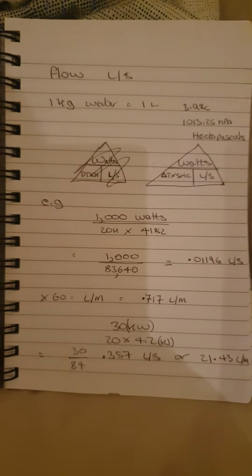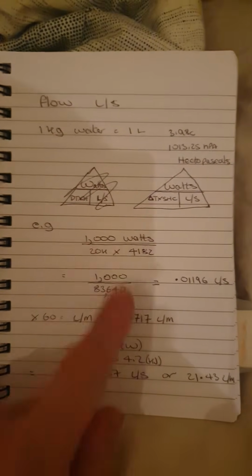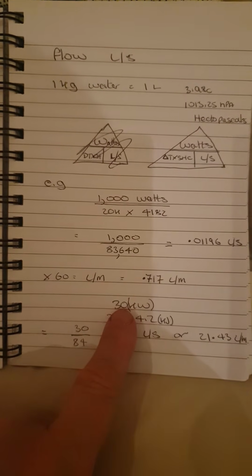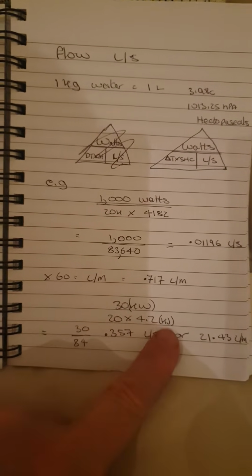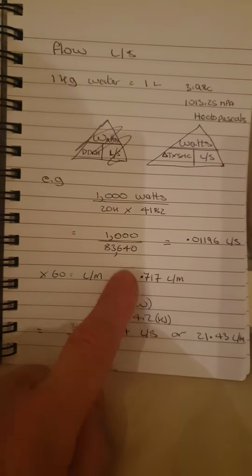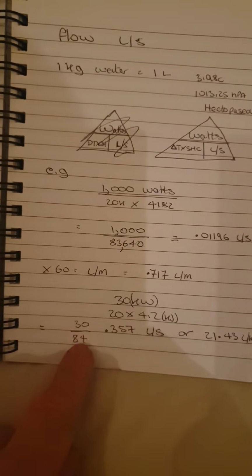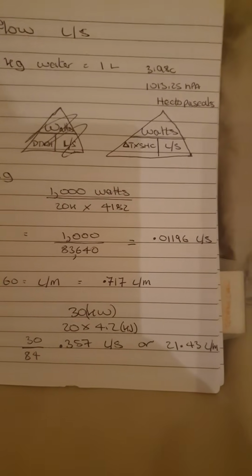Right, if you think in terms of a 30 kilowatt boiler then, rather than a 1 kilowatt radiator, we can actually use the kilowatt values by changing the joules to kilojoules. So we have 30 kilowatts divided by delta T20 multiplied by 4.2 kilojoules. And that conveniently, 4.2 kilojoules, by the way, is a rounding up of the 4182. So, which gives us this handy number of 84. 30 divided by 84 is 0.357 litres per second.